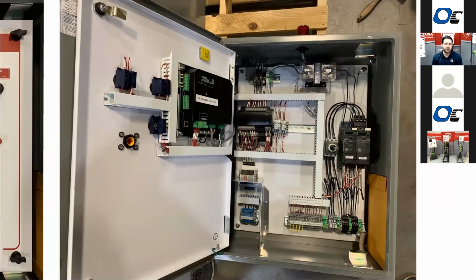And that is generating a very low energy signal out to the level control devices in the basin. Whether it's float switches or a pressure transmitter, it's a very low energy signal that's not going to cause a spark or short or something that would lead to igniting the hazardous gases. So all of that wiring would come in here, and that would give us a specific point for the field electricians to tie in and do their requirements for the intrinsically safe wiring between our panel and the pump itself, or the pit itself.